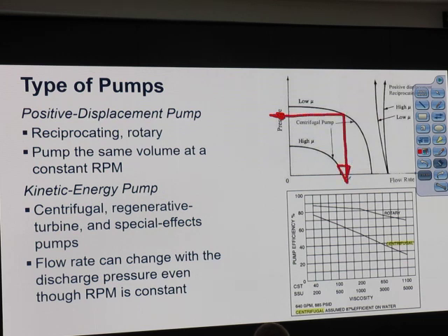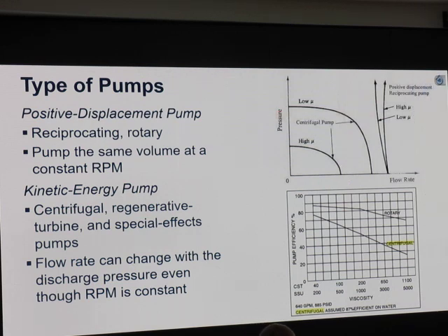At that pressure drop, maybe 15 psi, what is the flow rate that it can produce? Will it produce more than the rate that you want, or less? If it produces less than the rate that you want, this means that pump won't deliver at that flow rate when the pipe is that size. That's how you size it, but first, let's take a look at the type of the pump.